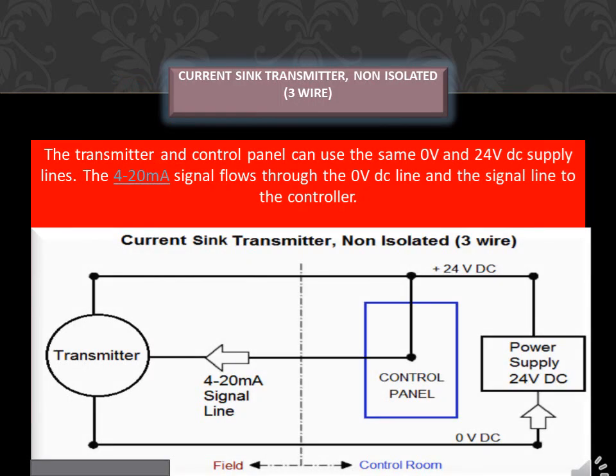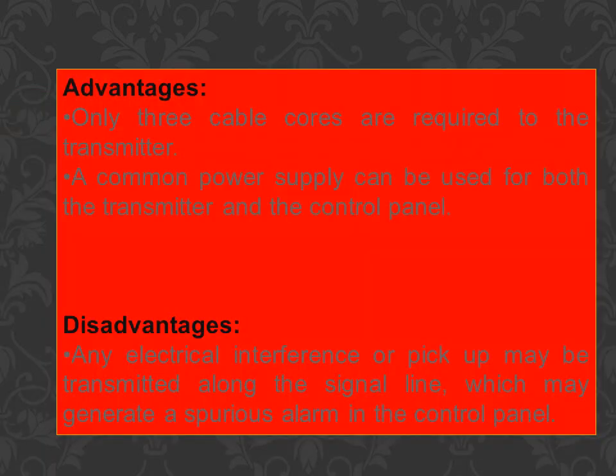Current sink transmitter, non-isolated, 3-wire. The transmitter and control panel can use the same 0V and 24VDC supply lines. The 4-20mA signal flows through the 0VDC line and the signal line to the controller. Advantages: only 3 cable cores are required to the transmitter, and a common power supply can be used for both the transmitter and the control panel. Disadvantages: any electrical interference or pickup may be transmitted along the signal line, which may generate a spurious alarm in the control panel.